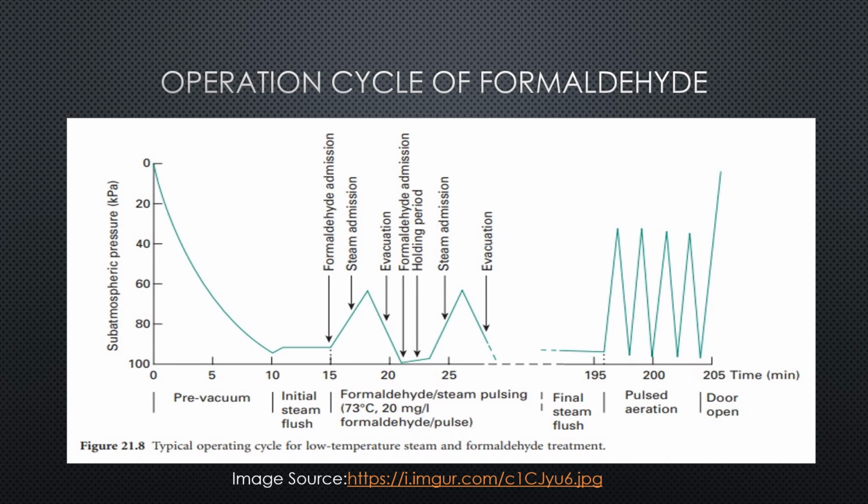The chamber temperature is maintained by a thermostatically controlled water jacket. Again, water will be flowing so that the temperature is maintained, and steam and condensate are removed via a drain channel and an evacuated condenser. At the end of a treatment period, formaldehyde vapor is expelled by steam flushing.